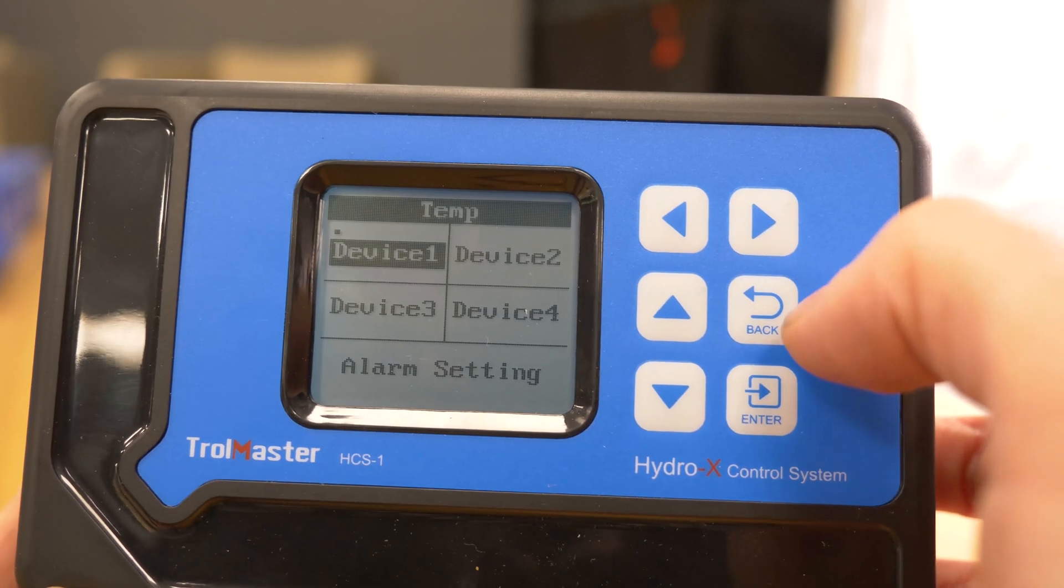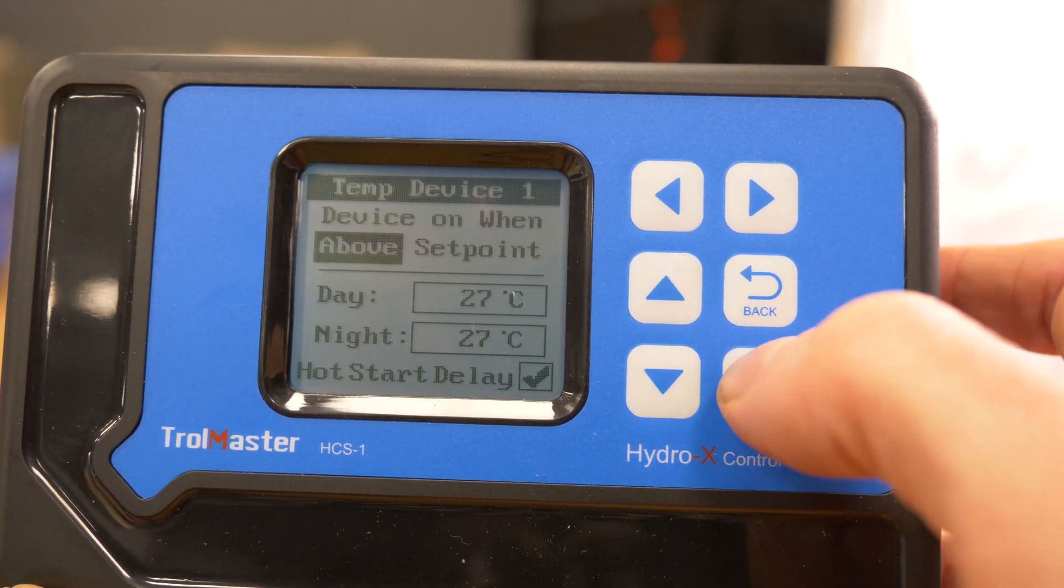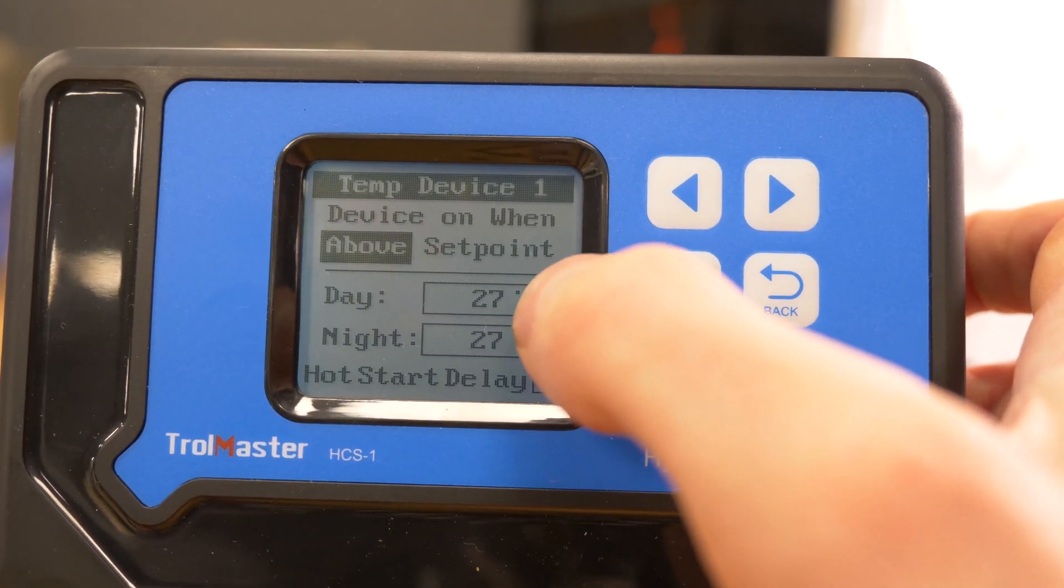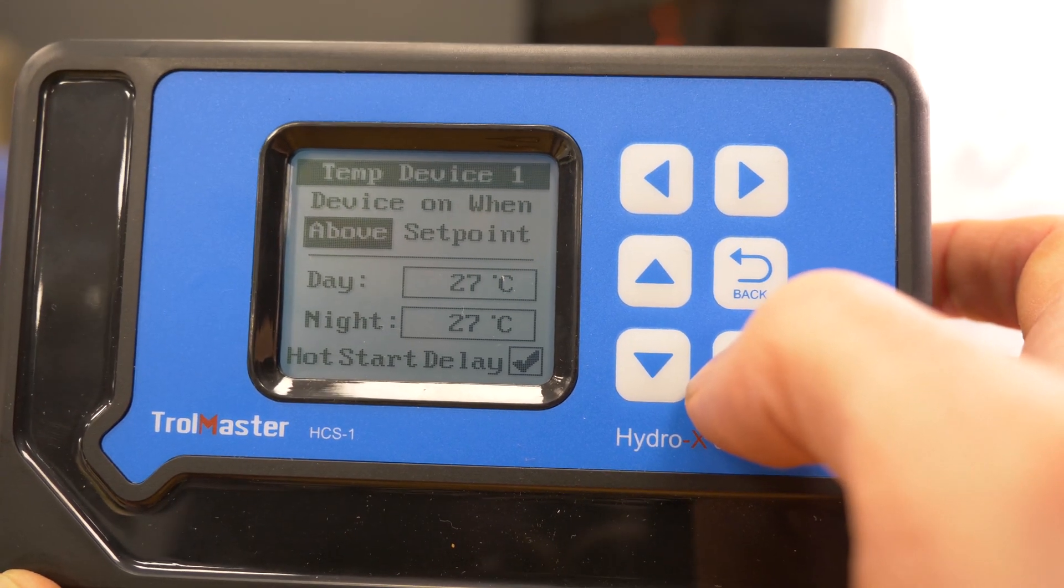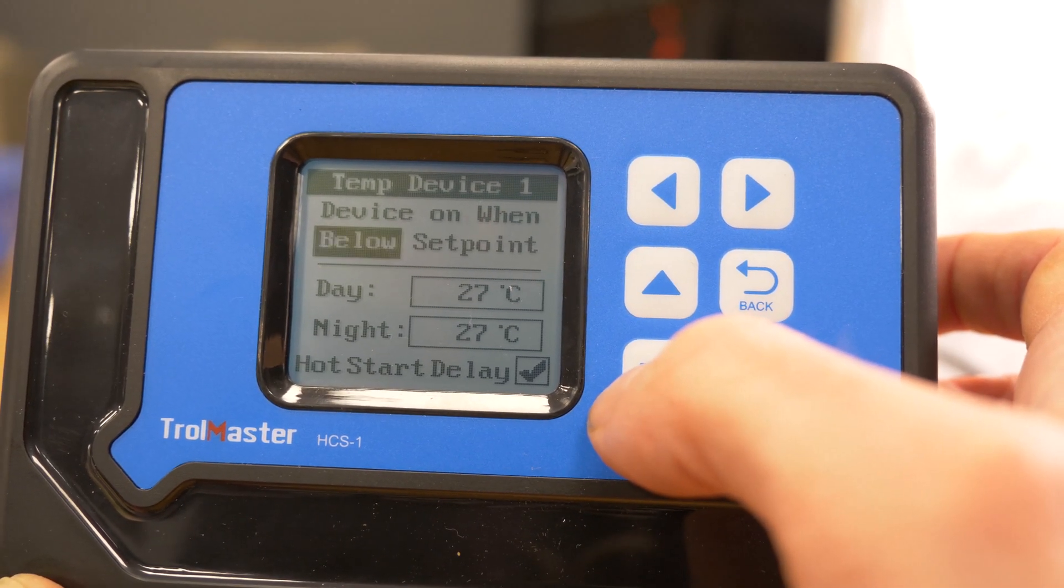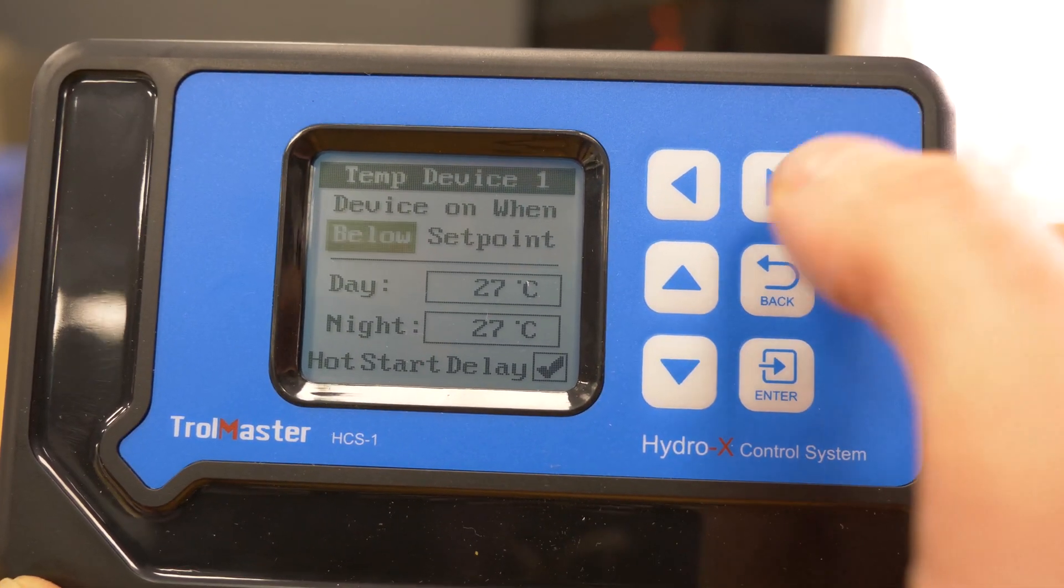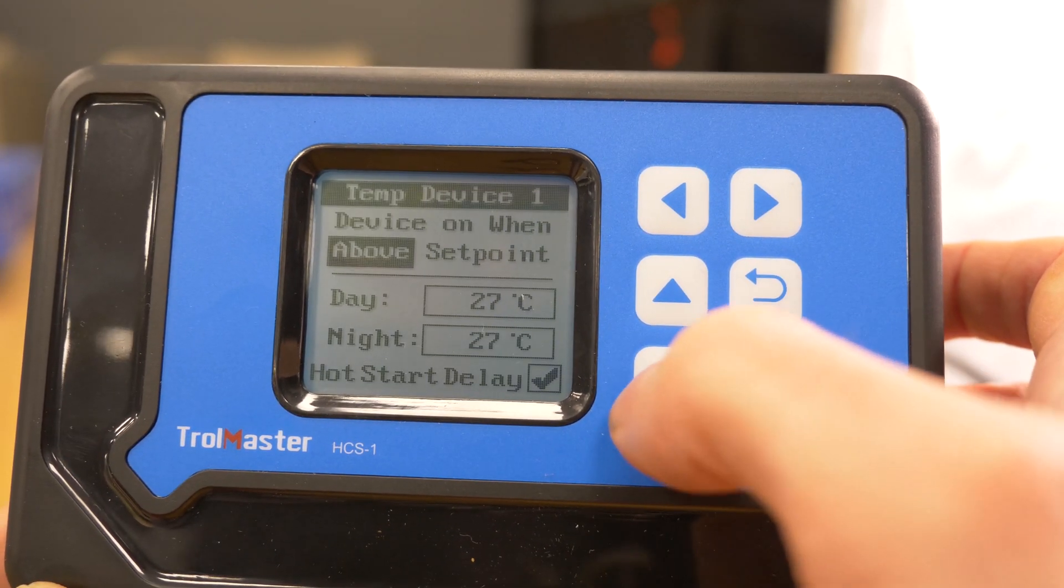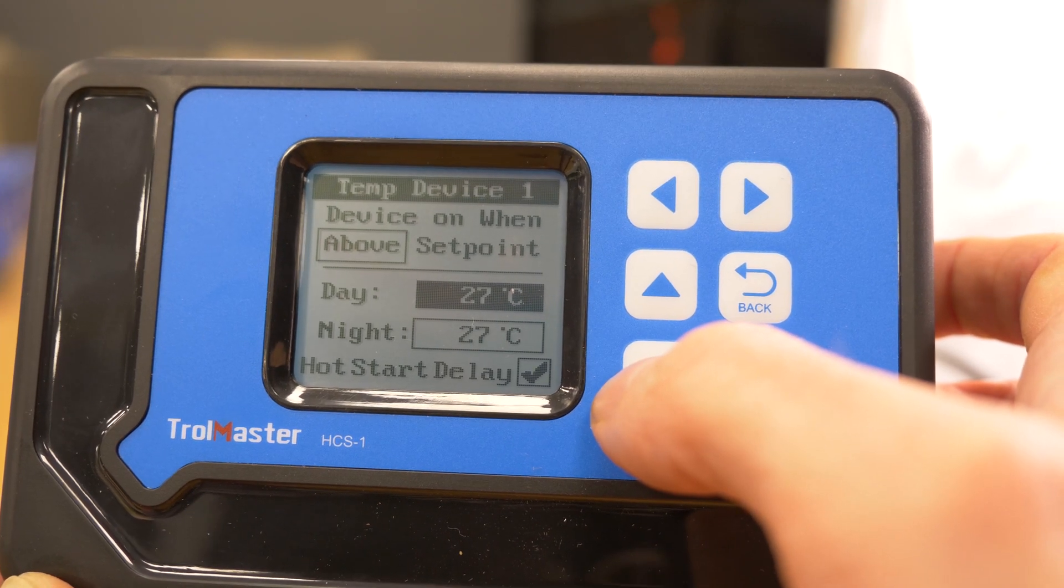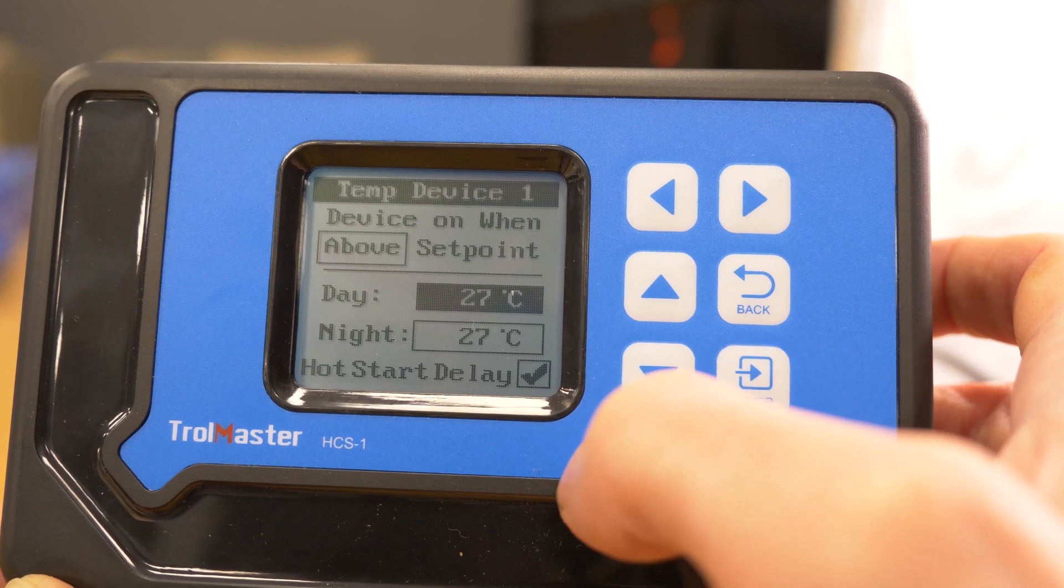On device one you can have multiple devices so you could have heaters, coolers, ACs whatever. You can set the device to go on when above or below a certain set point. So heater you'd be setting it below a set point say 15 degrees centigrade and in this case we've got the cooler coming on at 27 degrees and we don't want to get things too hot.